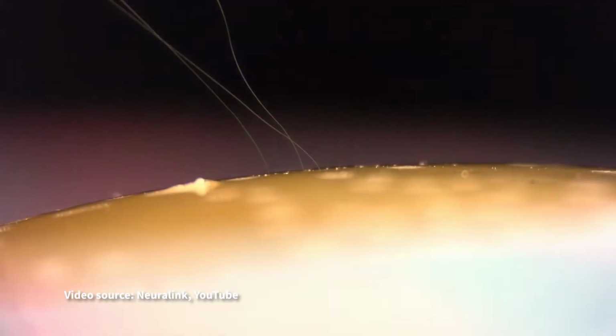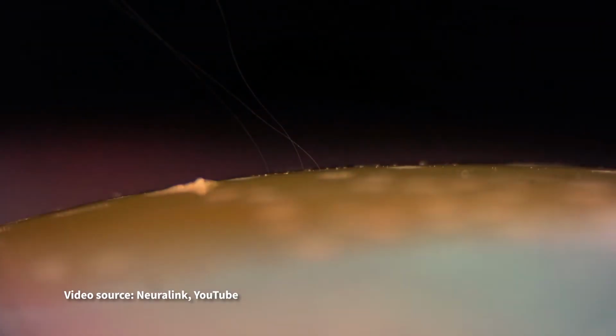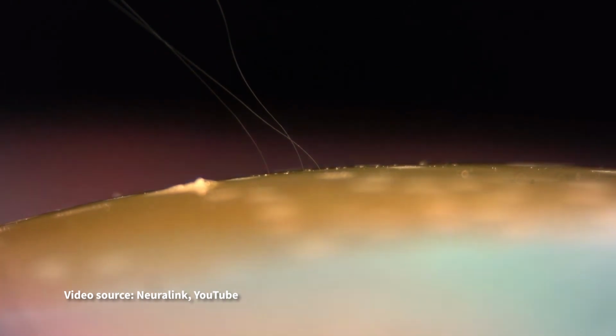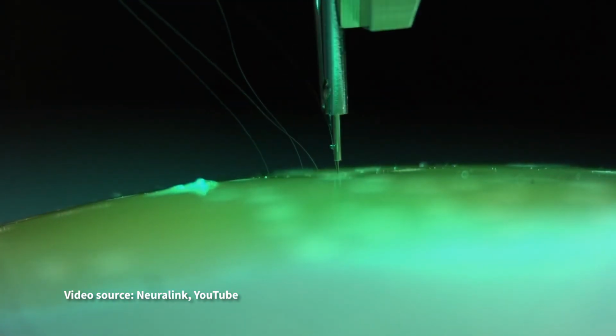The pincher is made of 50 micrometer diameter tungsten wire with a bend at the tip, and it's driven both axially and rotationally. Its purpose is to support the probes during transport and to guide the threads so that they follow the correct path during insertion. The insertion process can be automated, but at this stage the neurosurgeon will have full control of the robotic electrode inserter.